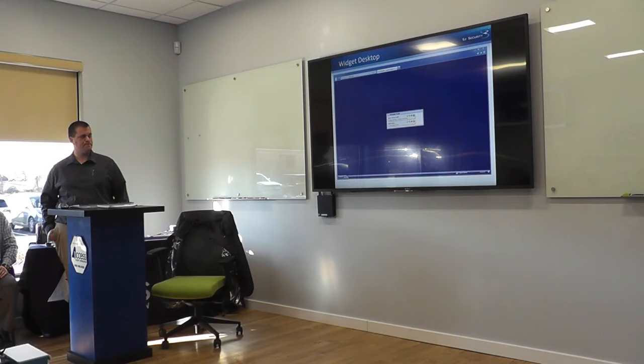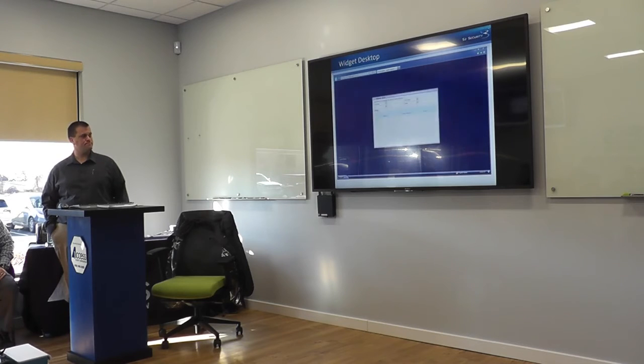The Intrusion Panel widget lists all available intrusion panels in selected partitions. Monitoring personnel can use the widget to view configuration and status information for the panels. The Passback Grace widget is used to grace people from passback and tailgate violations. Once an individual is graced, his or her next card read will be allowed and no violations will be triggered.